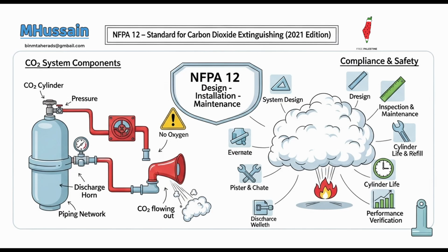Dirt traps, consisting of a T with a cap nipple at least 2 inches long, are required at the end of each pipe run to prevent blockages, acting as a last-line defense filter. Catch debris before the nozzle. Catching any tiny debris before it can clog a crucial nozzle, because even a speck could compromise the system when lives are on the line. Good idea. What about the pipe fittings?